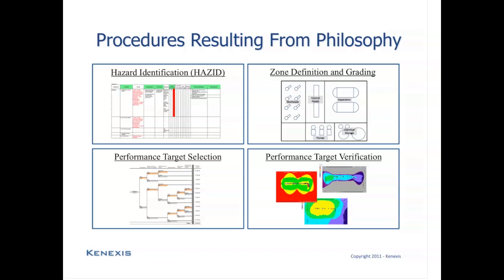Some of the procedures that are going to result from the development of an FGS philosophy will include a hazard identification procedure, which is going to allow you to determine whether or not hazards are present, and if so, what type of hazards are present. Then there's going to be a procedure for defining zones and setting grades and extents of the grades for those zones. Then you'll have another procedure for establishing performance targets or setting performance targets for the equipment. And finally, you will have rules, procedures, and probably even standardized tools for assessing that the performance targets have been achieved. So tools for verification of the performance targets of safety, availability, and detector coverage.